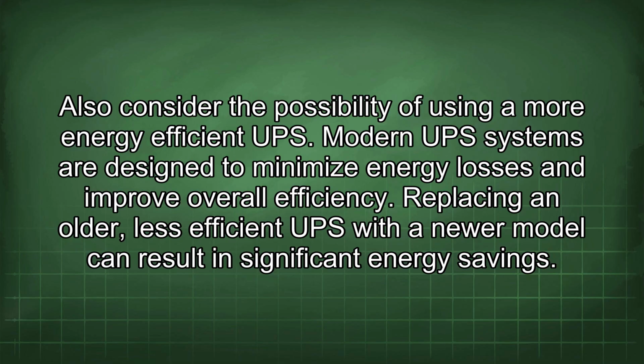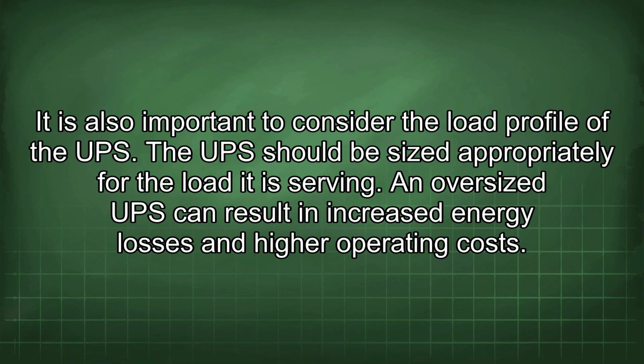Also consider the possibility of using a more energy-efficient UPS. Modern UPS systems are designed to minimize energy losses and improve overall efficiency. Replacing an older, less efficient UPS with a newer model can result in significant energy savings. It is also important to consider the load profile of the UPS.